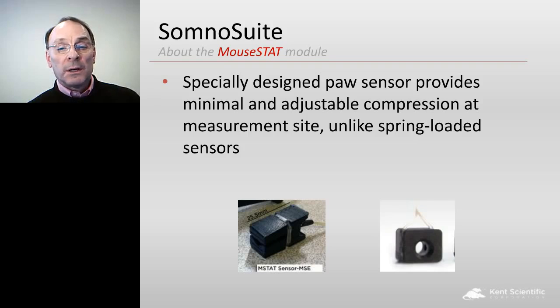There are two sensors available. There's a little clip which has just a very lightweight rubber band on the outside, so it's not spring loaded, and the hinge is rather stiff so that you can position it and it will stay there, but will not increase the pressure on the animal the way a spring sensor will. Or we have other special use sensors, which are essentially non-contact, which we call the annular sensors, which have just a hole through them. The one on the right is a 4mm sensor that slides over the animal's paw.